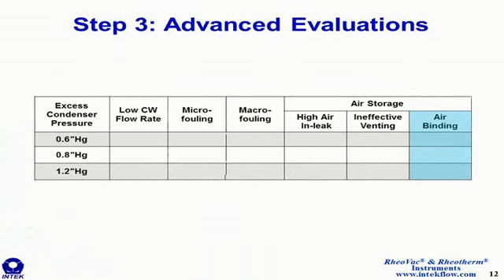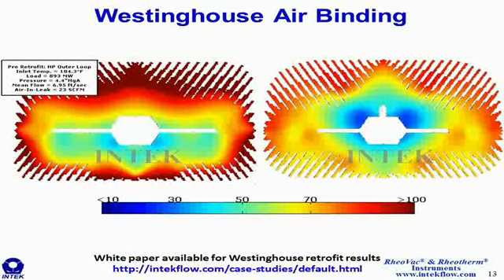The last example of air storage, I have 2 case studies here that show air binding. And in these 2 case studies, I'll show results of a retrofit where we eliminated the air binding and recovered significant performance improvements. So these are Westinghouse condenser bundles. These are the performance profiles with no retrofit in place. These condensers are known to be poor performing condenser designs. You can see with very low air in-leakage into these bundles, you can see it up there in the legend, the air in-leakage to this shell where there's 4 of these bundles is only 23 SCFM. And you can see that the performance profile shows that about half the tubes are affected with air binding.